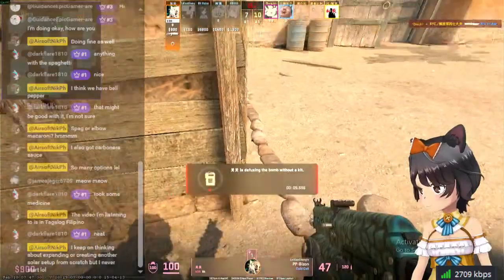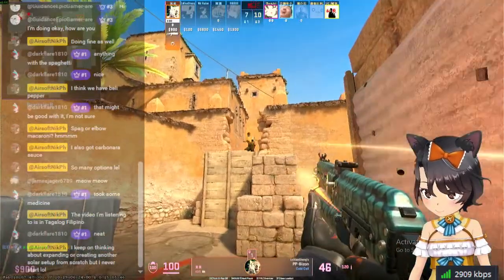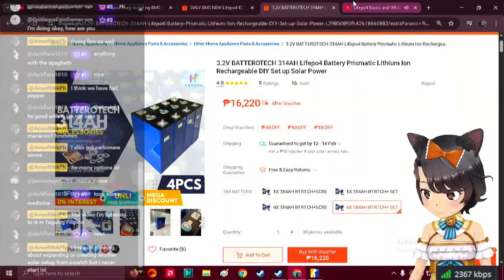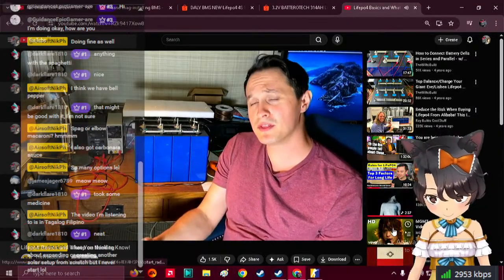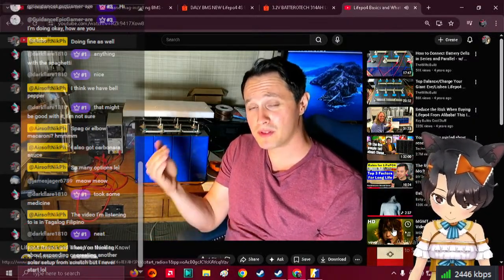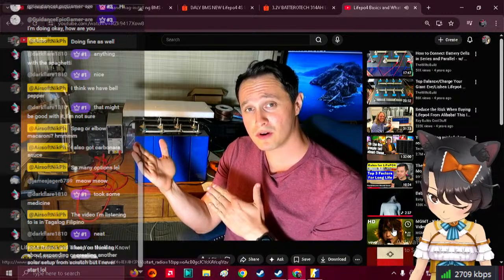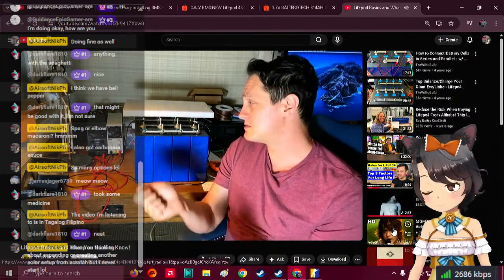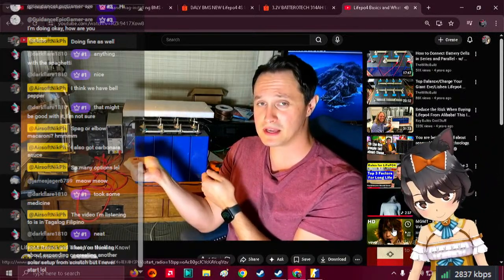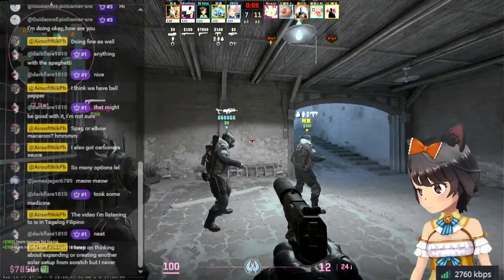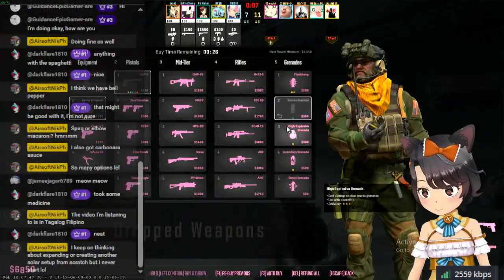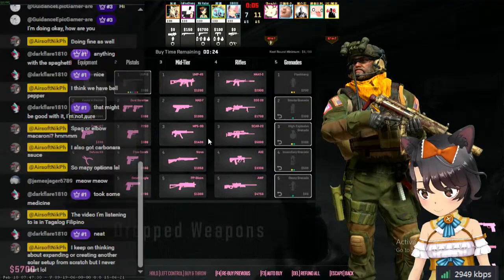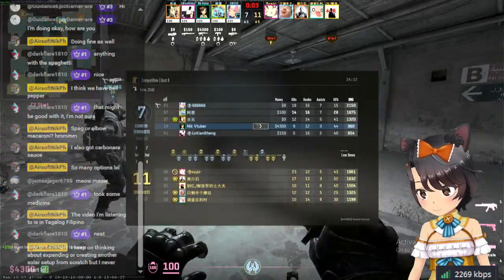Alright, when you're talking about voltages: the voltages on your batteries and cells are always going to dip when they're under load. They'll dip more at the high end or low end of the curve under load. But you never want to test the voltage of your batteries under load and take that as gospel—make sure you remove the load, whether charging or discharging, and test without anything on them to get the actual voltage.